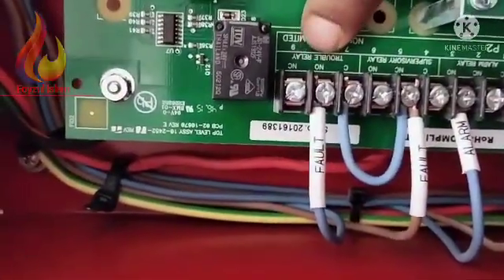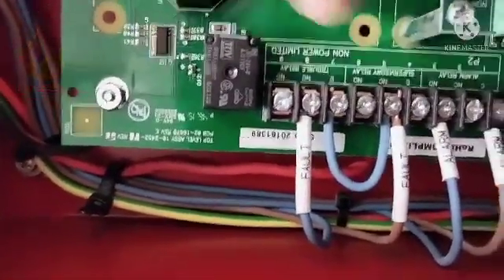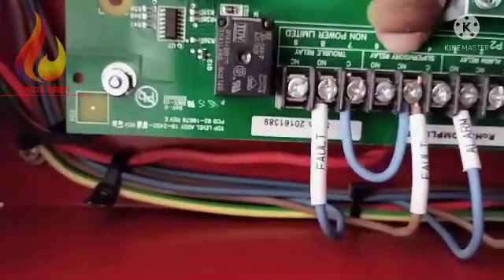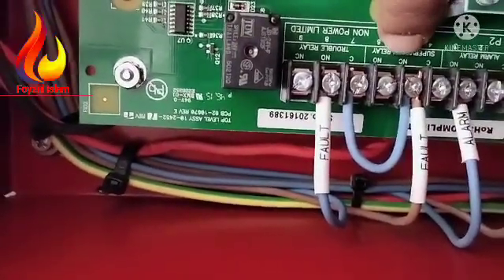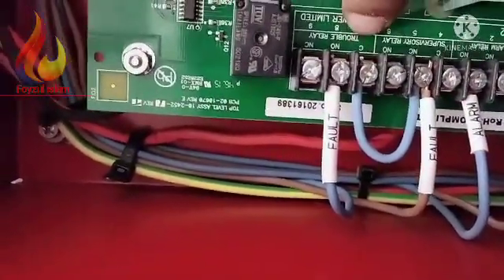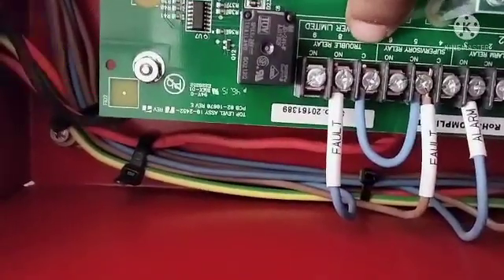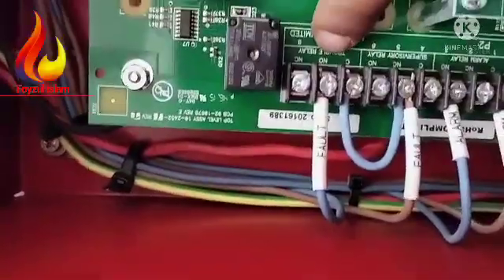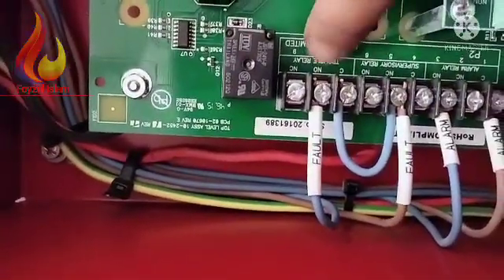This is the trouble relay and supervisory relay. I have already connected it in normally closed condition - brown - and from brown to trouble common we connect it, making one loop. The brown-blue cable we connect to the trouble relay in normally open condition.